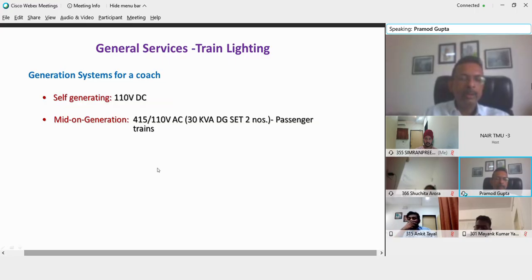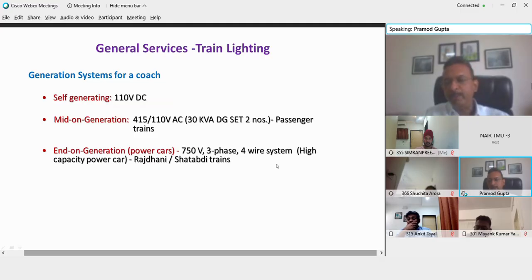The third one is the end-on generation system, where we use power cars to generate electricity, with DG sets in the power car. The output of the DG set is fed to the coaches using a 750 volt 3-phase 4-wire system. These power cars are high capacity, since we have two power cars per train, each equipped with two DG sets. So in a Rajdhani or Shatabdi kind of train, we have 4 DG sets placed in two power cars, and at a time we use either two or at most three DG sets to meet the entire load, with the redundant capacity taking care of any additional requirement.